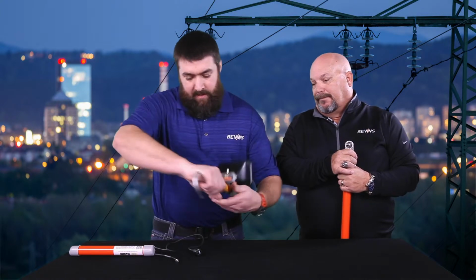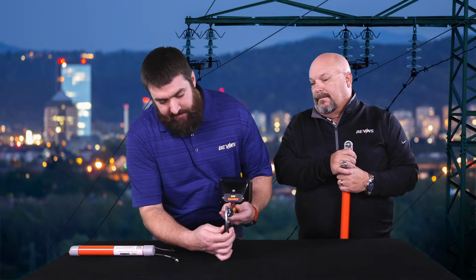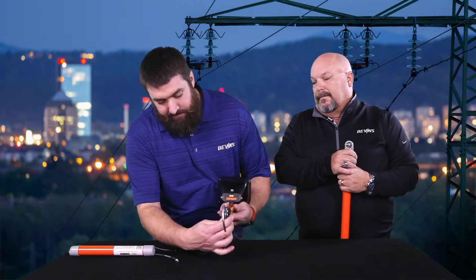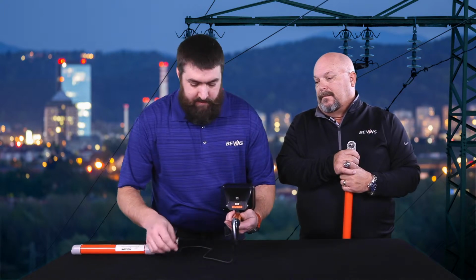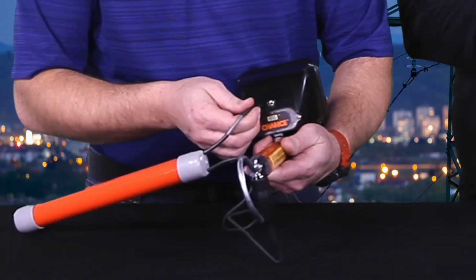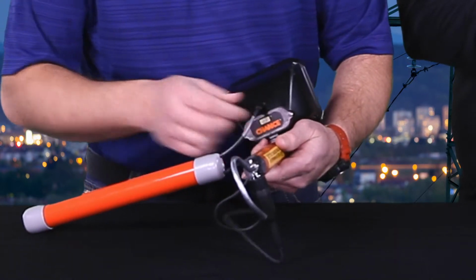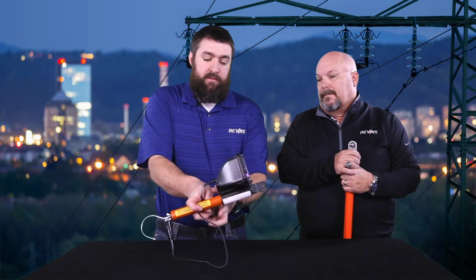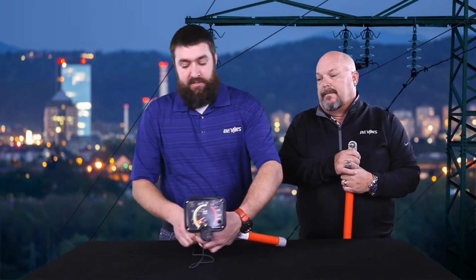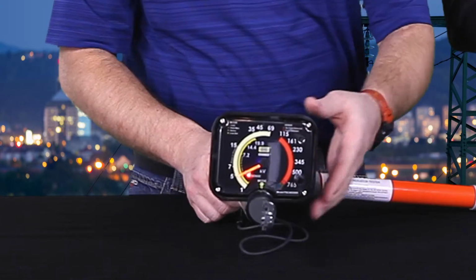What I'm going to do is attach the input clip from the field tester onto the unit, then plug this jack into the front nose, and we're going to see an indication. The tester basically simulates a high voltage signal, so we've injected something through the input, and we should see somewhere around 5 kV.